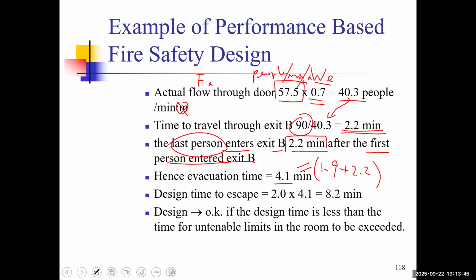Design time to escape, and the design is okay if the design time is less than the untenable limits in the room to be exceeded. So this is an example of how performance-based fire safety design is used to consider the means of escape, the evacuation time. The most important thing is that the design time should be less than the time for the untenable limit in the room to be exceeded.